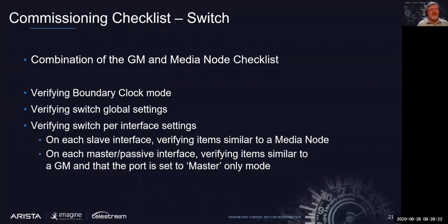If we look then at the checklist for a switch, most of them will be in boundary clock mode. You're effectively acting almost like a media node at the bottom because you're receiving the timing information, but on all your other ports, you're acting effectively as a grandmaster, and so you're sending the time down. So the checklist for a switch is basically a combination of both the grandmaster's checklist and the media node's checklist. One thing on the switch checklist is that you want to verify your boundary clock settings. Typically in the switches, there are 2 groups of settings. There are some which are globally applied, so you want to check the globally applied settings, as well as every single interface, which has certain settings related to it. So you're going to have to check each interface and make sure they are configured properly, for instance, like that master-only control.